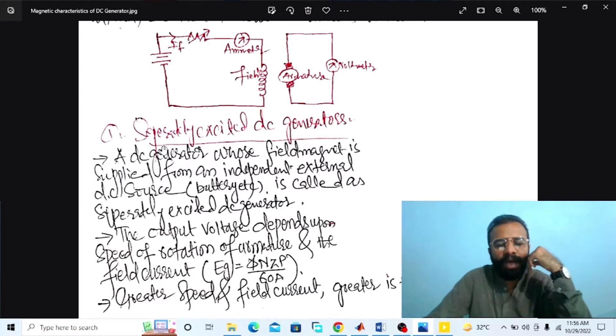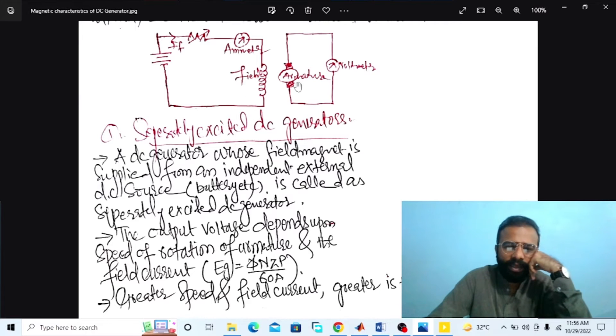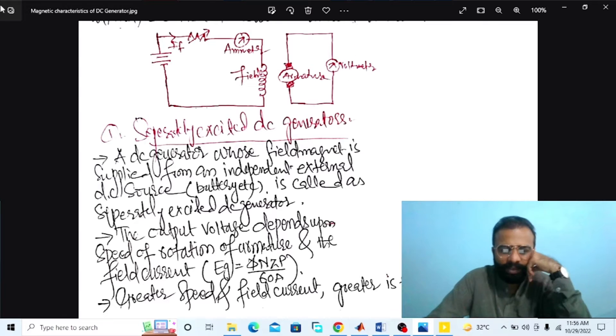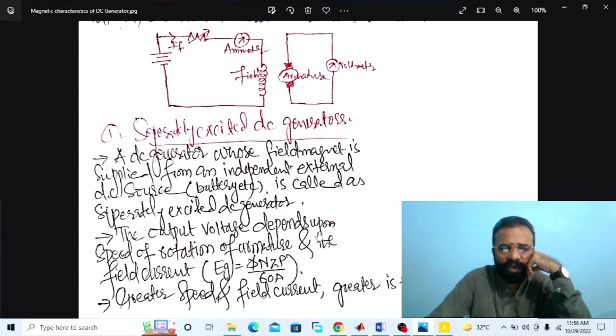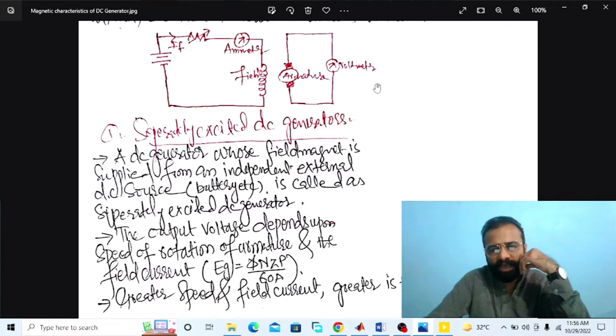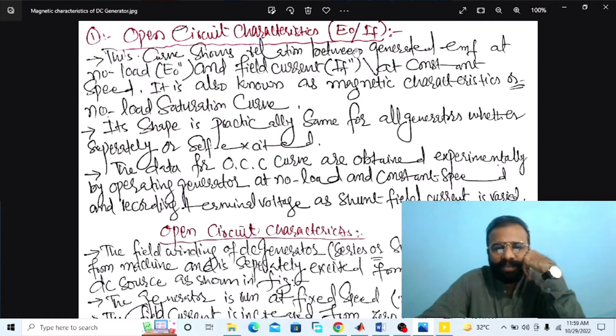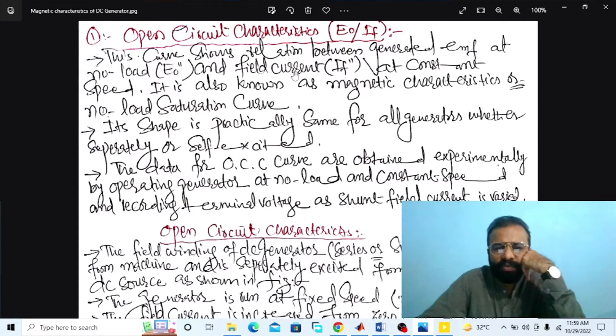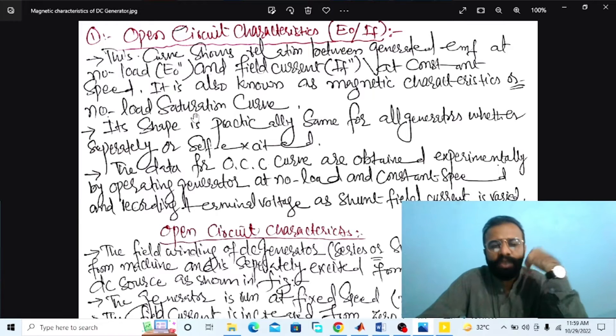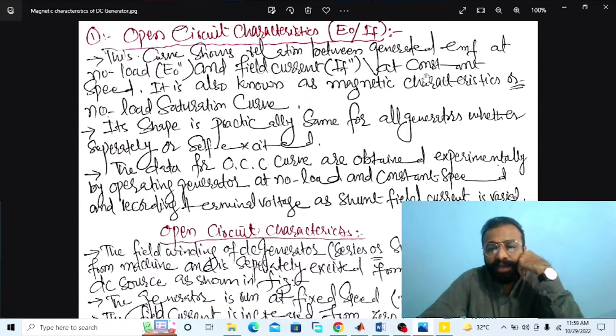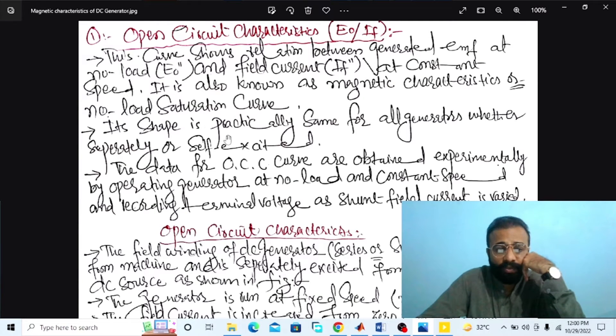If we increase the RPM of a DC machine, the generated EMF will also increase. So greater the speed and the field current, the greater will be the generated EMF. The open circuit characteristics of a DC generator is a curve showing the relation between the generated EMF at no load and the field current at constant speed, called the magnetic characteristics or no load saturation curve.